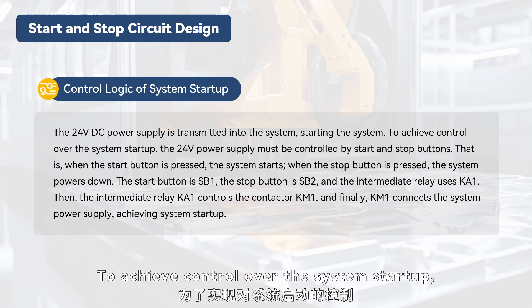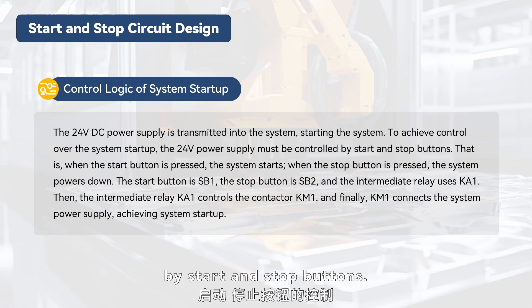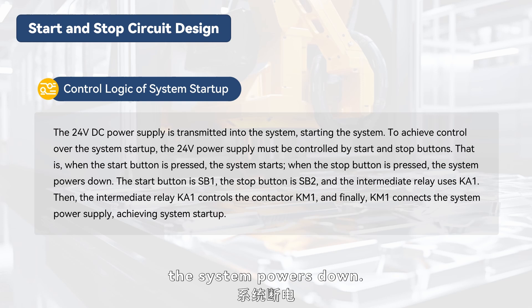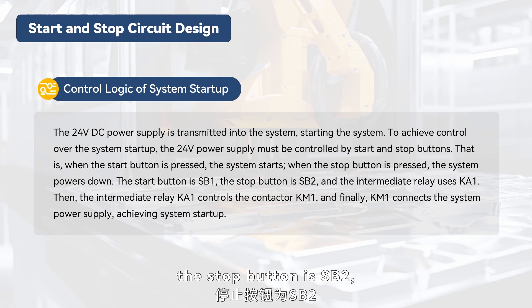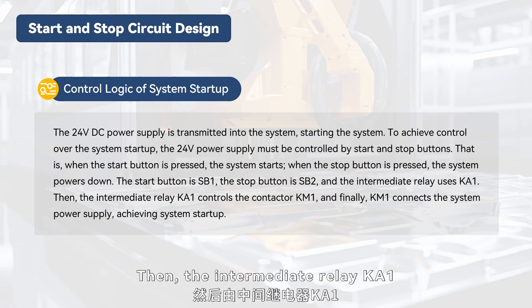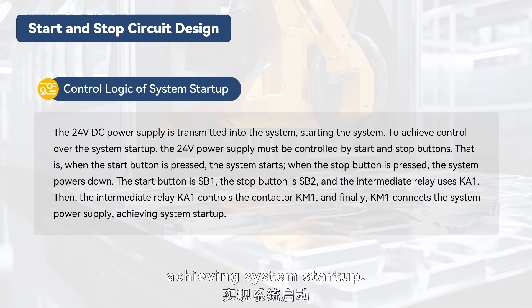To achieve control over the system startup, the 24 volts power supply must be controlled by start and stop buttons. When the start button is pressed, the system starts. When the stop button is pressed, the system powers down. The start button is SB1, the stop button is SB2, and the intermediate relay uses KA1. The intermediate relay KA1 controls the contactor KM1, and finally KM1 connects the system power supply, achieving system startup.